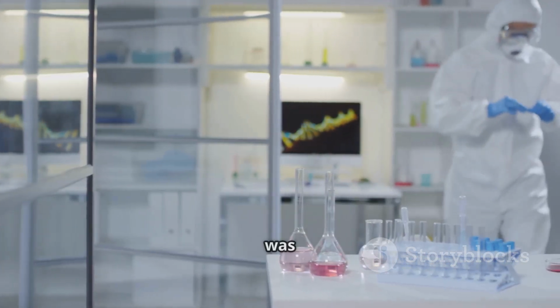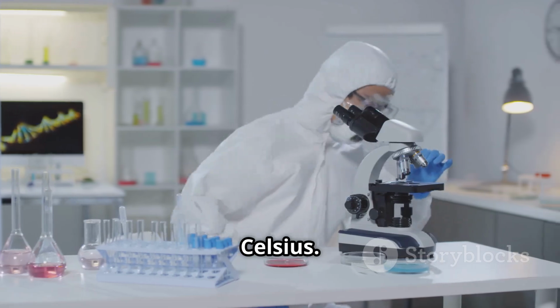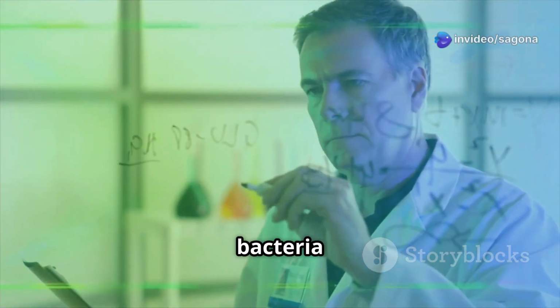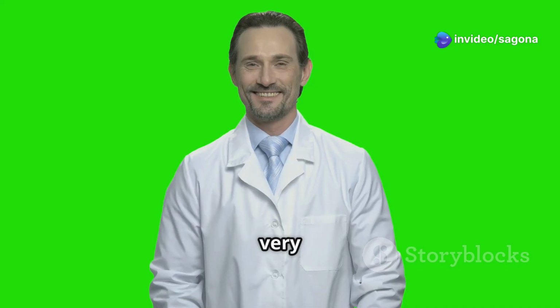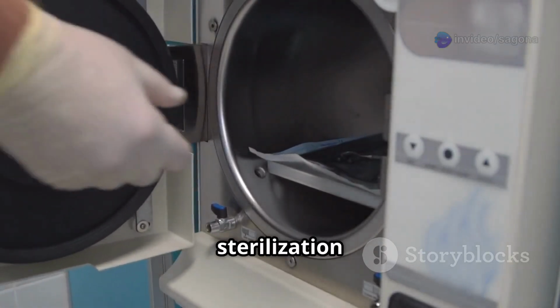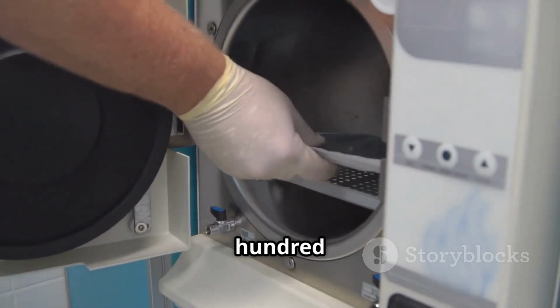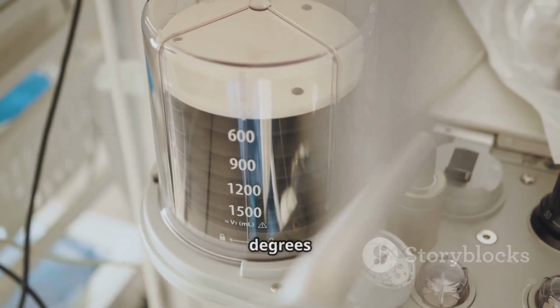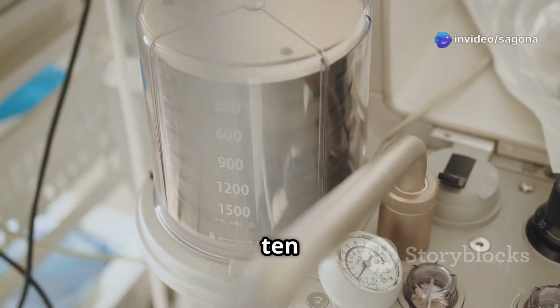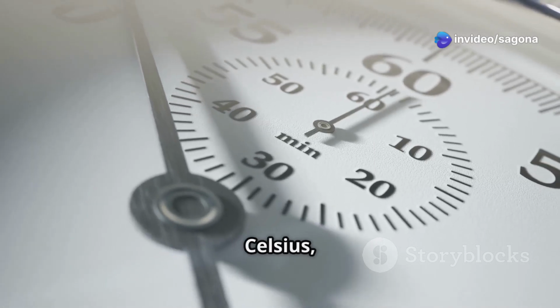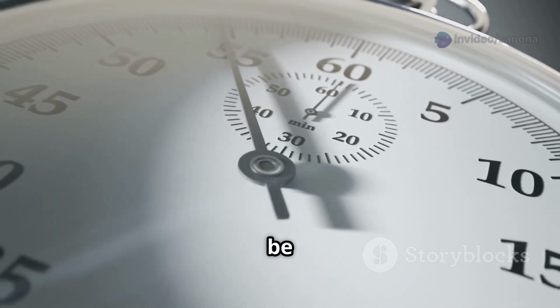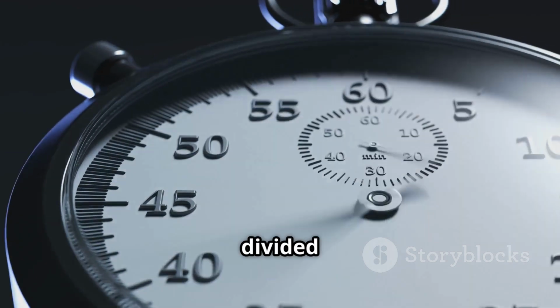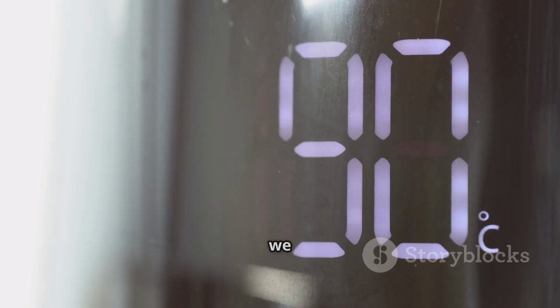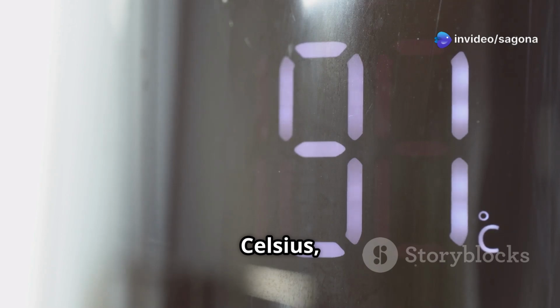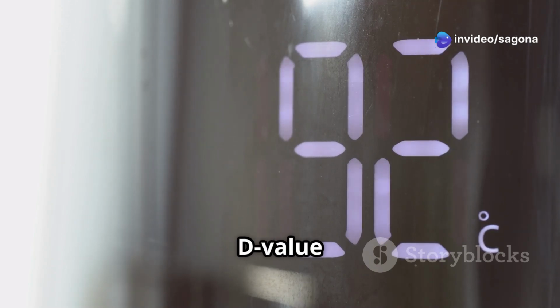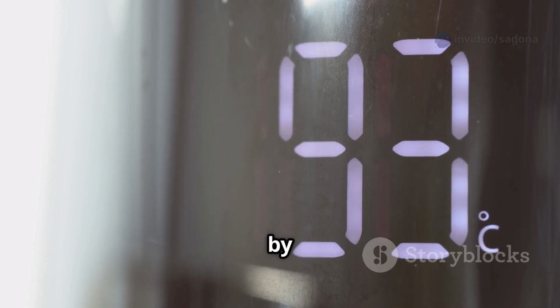Let's go back to our example. We said its D value was 2 minutes at 121 degrees Celsius. Now let's say the Z value for these bacteria is 10 degrees Celsius. This tells us something very useful. If we increase the sterilization temperature by 10 degrees Celsius, from 121 degrees Celsius to 131 degrees Celsius, the D value will become 10 times smaller. So at 131 degrees Celsius, the D value would only be 0.2 minutes. That's 2 minutes divided by 10. That's super fast. But if we lowered the temperature by 10 degrees Celsius to 111 degrees Celsius, the D value would become 20 minutes, 2 minutes multiplied by 10.